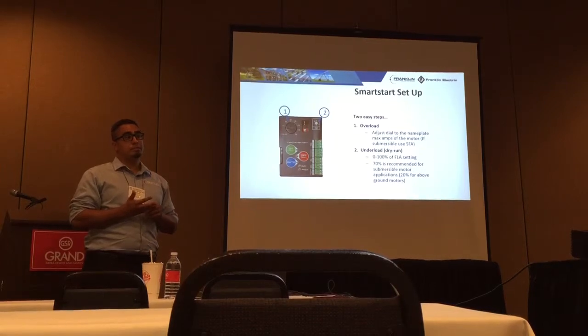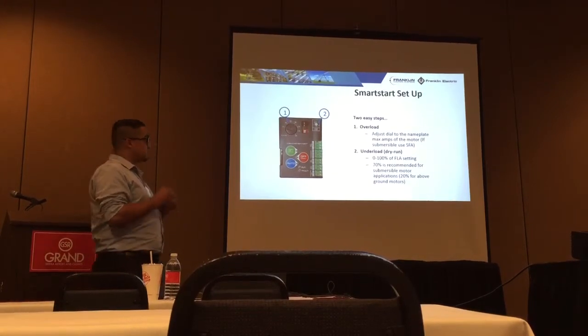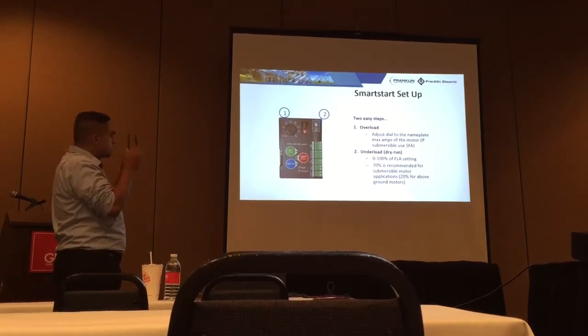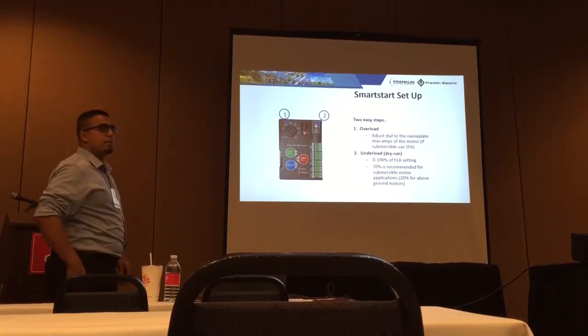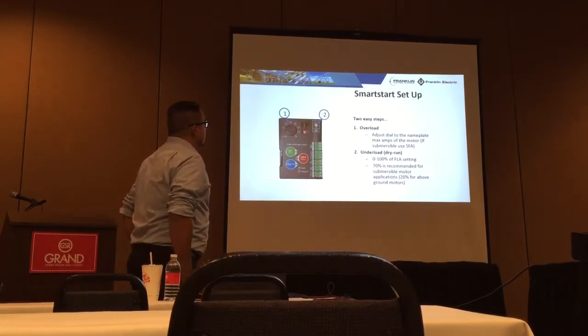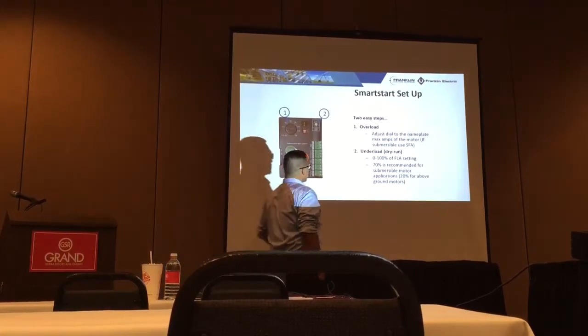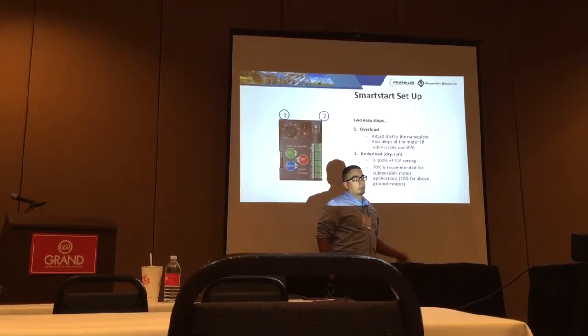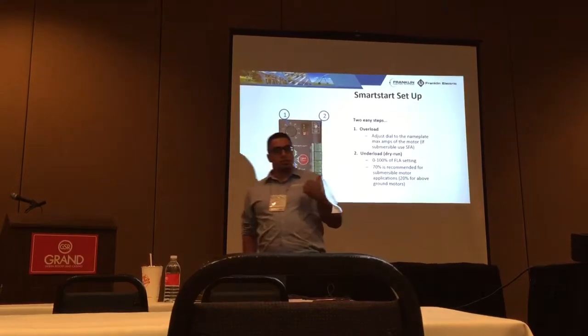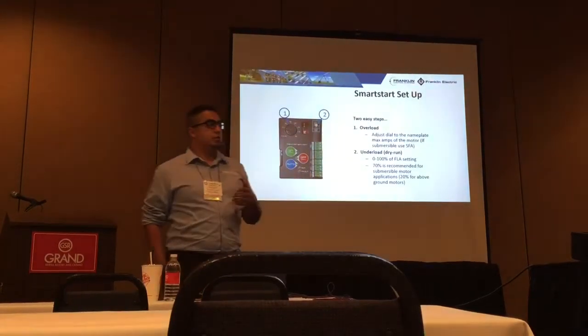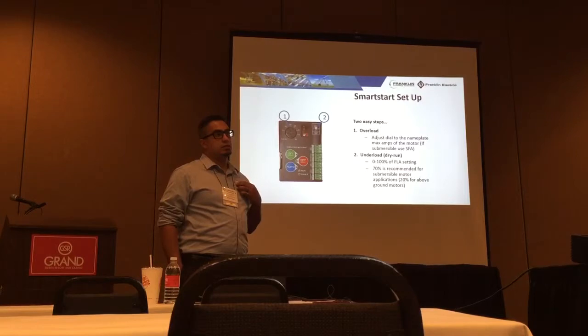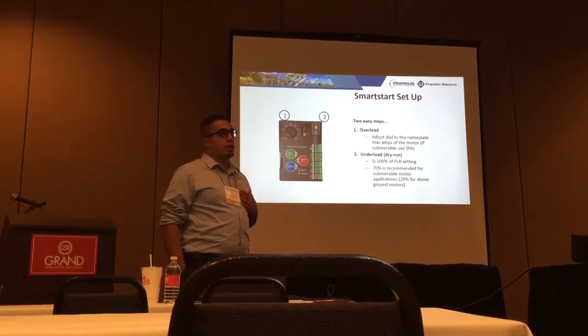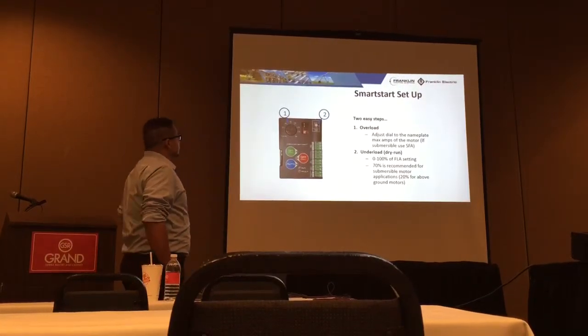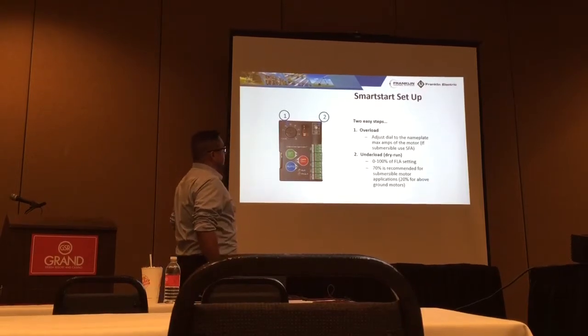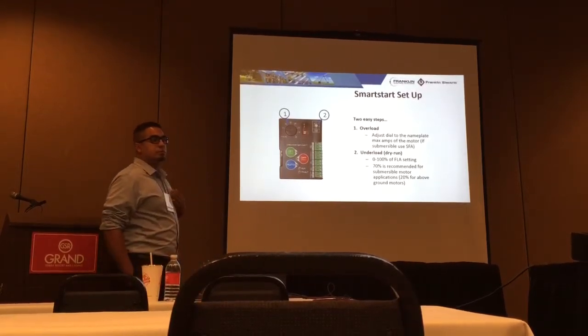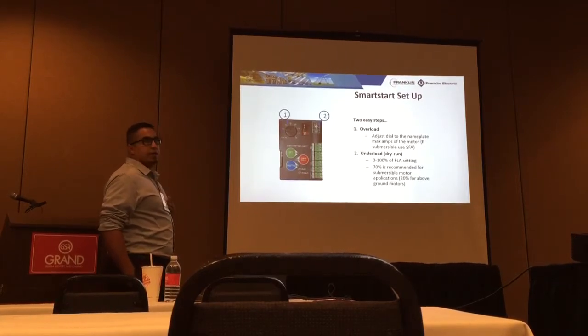I do. Another question is why on the percentage where you can turn down your underload, why do you guys even have below 70 if you don't recommend running below 70? Why don't you just have an off and then 70? So we use the same overload on surface motors, which will typically pull about 30–40% on no load currents. Gotcha. Yeah. I mean, talking to you guys on the troubleshooting, they say never go below 70%, so it's like, why even? So that's submersible, and obviously centrifugal can be a little bit lower, yeah.